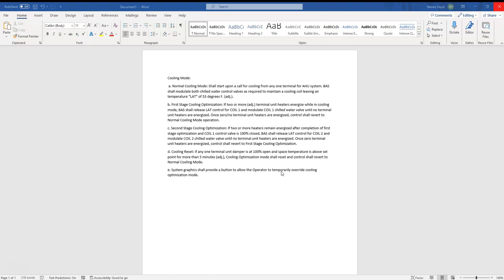Caveat is D: if any VAV unit is open 100% and the space temperature is above set point for five minutes, then we're going to go back to A. We can do this in the VAV and just send a signal to the air handler. That's going to be the easiest way to do that.